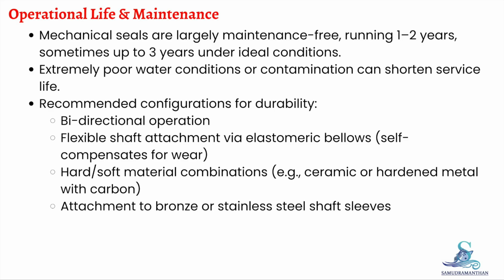Operational life and maintenance. Mechanical seals are largely maintenance-free, typically lasting 1 to 2 years, sometimes up to 3 years under ideal conditions. Poor water quality, sediments, or overheating can shorten their lifespan.